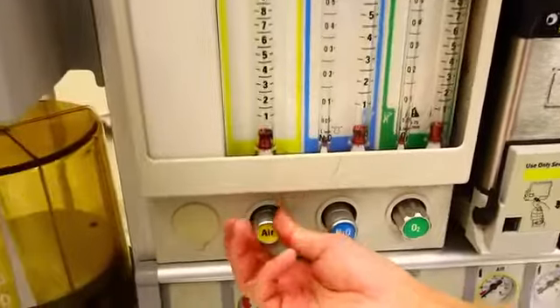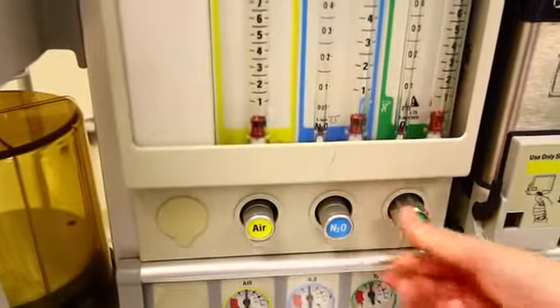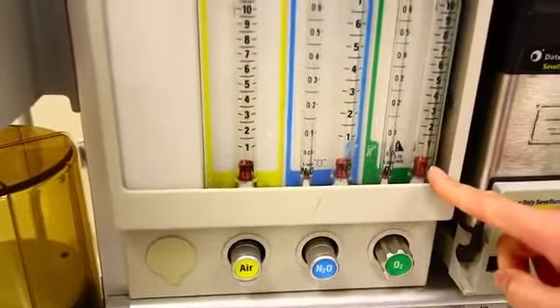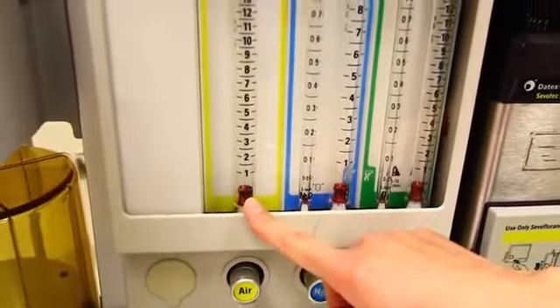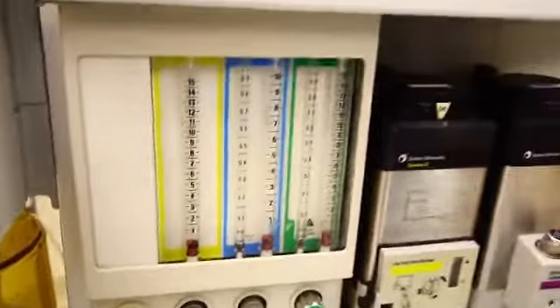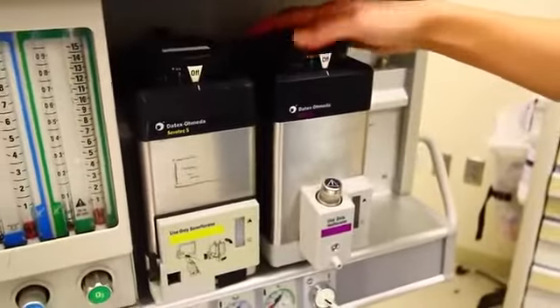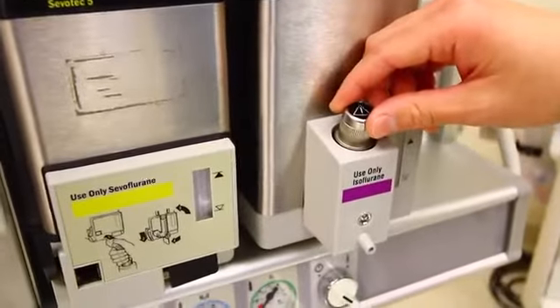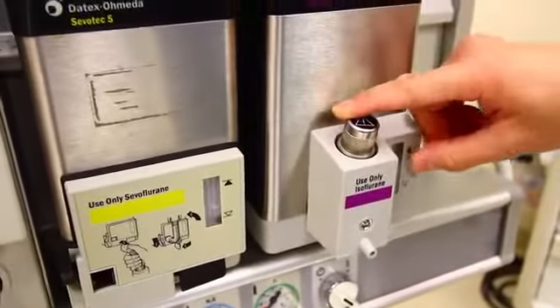The next thing is to check the low pressure system. Close the flow control valves by turning the knobs clockwise. Also note that the floats are at 0. Now make sure the vaporizers are in the off position. And if applicable, tighten the fill caps and check the fill level.